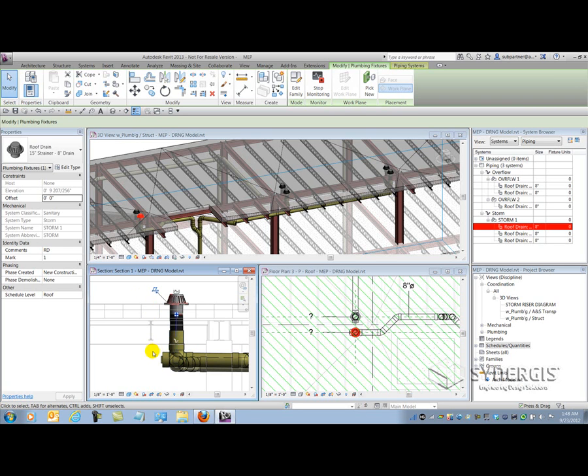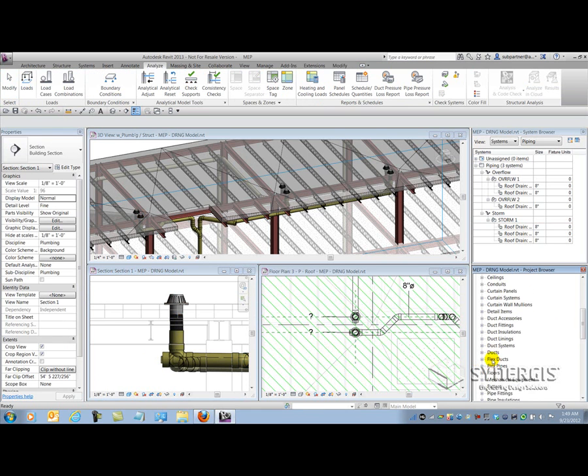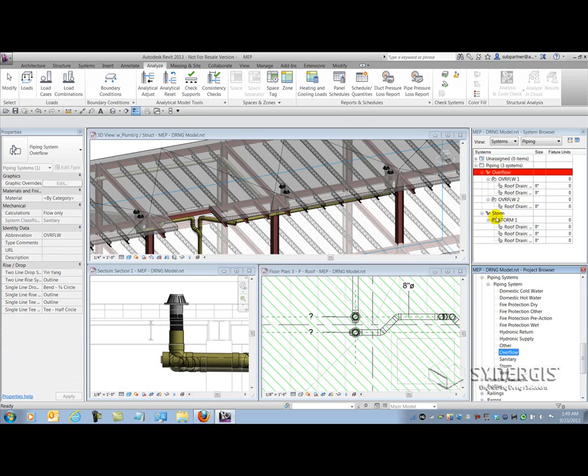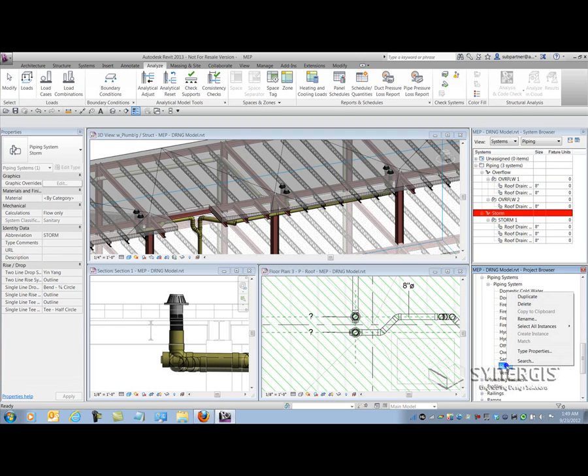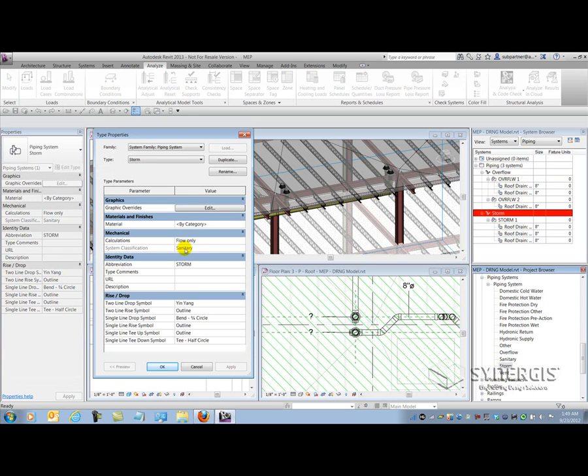It's not giving me any relevant data as far as flow is concerned. One thing to note about sanitary systems in Revit is that they don't track flow. The only way you can track information through a sanitary classified system is through fixture units. This is easy to confirm if you go down to Families and look at your piping systems. Here you can see I've built Storm and Overflow, which are highlighting in my system browser through my logically connected networks of drains. Right-clicking on Storm and looking at type properties, you can see it's based off the sanitary system classification and it's calculating flow.